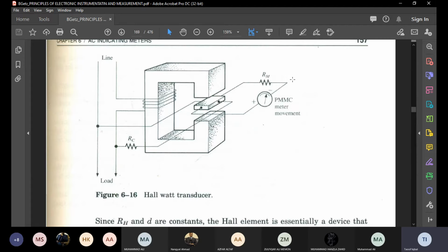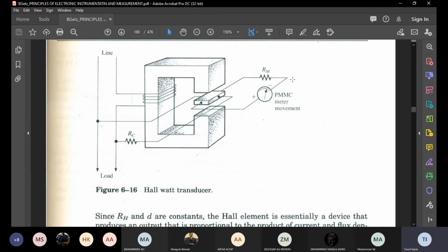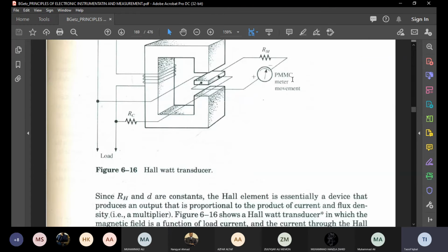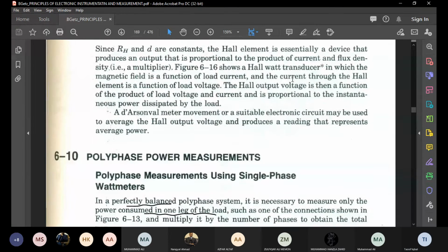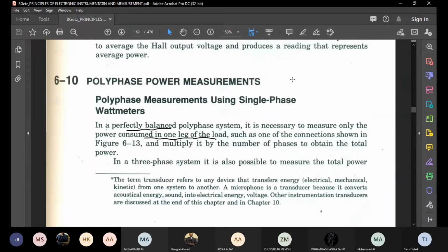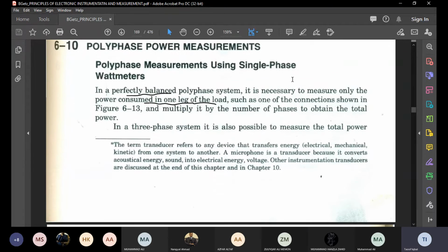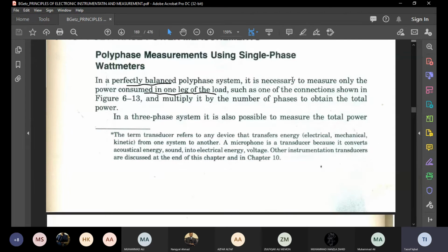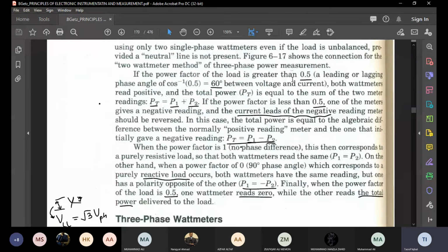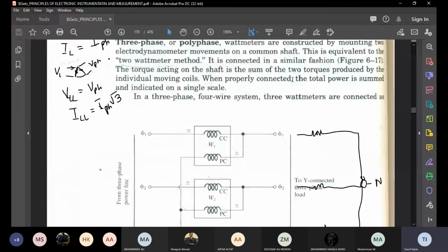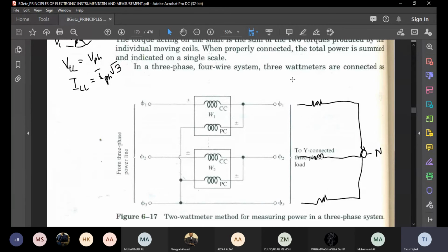We get the voltage out of the Hall effect sensor, and that voltage is used to measure the power of the wattmeter, from the line current and the voltage. Similarly, we can use the power meter, the wattmeter, to measure multi-phase power, like three-phase. So in three-phase, basically we are going to use two dynamometers or two wattmeters.